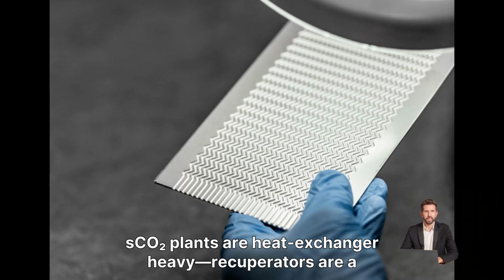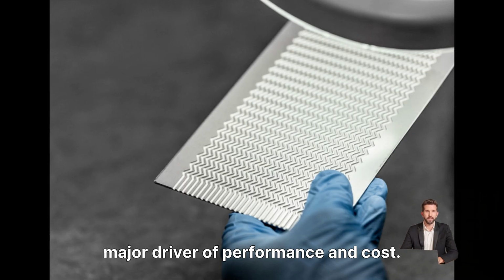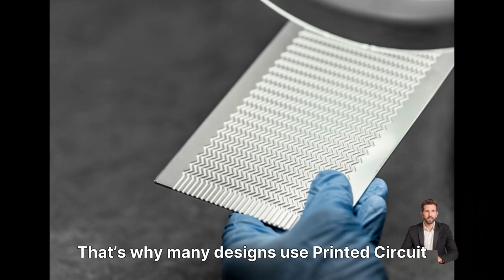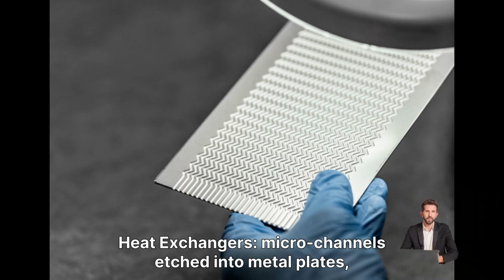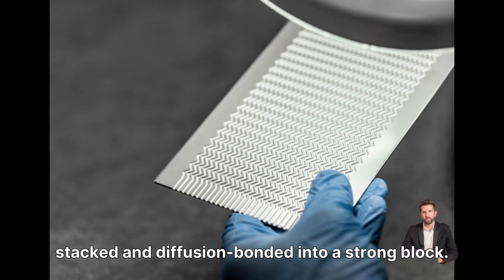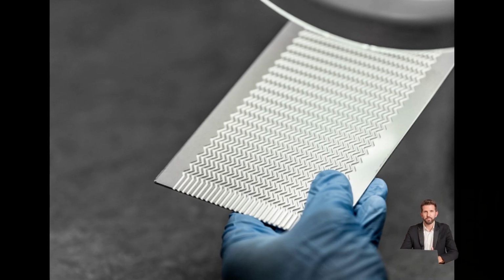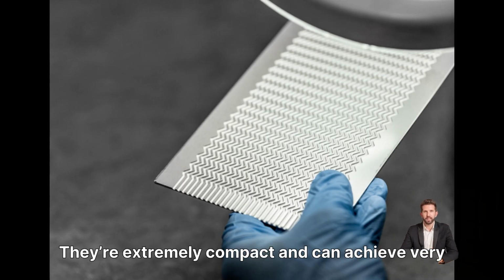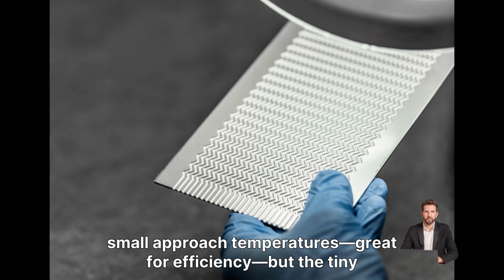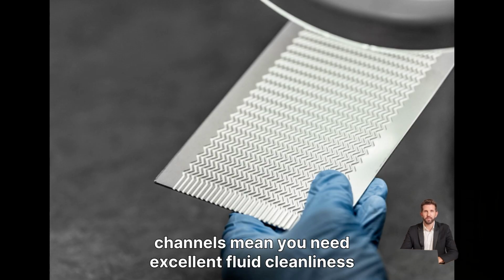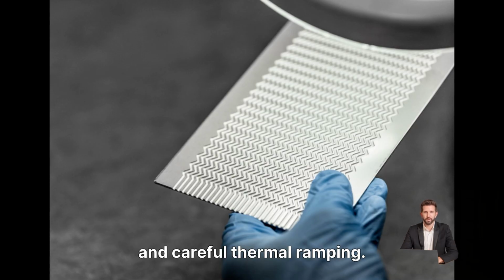SCO2 plants are heat exchanger heavy. Recuperators are a major driver of performance and cost. That's why many designs use printed circuit heat exchangers, microchannels etched into metal plates, stacked and diffusion bonded into a strong block. They're extremely compact and can achieve very small approach temperatures, great for efficiency. But the tiny channels mean you need excellent fluid cleanliness and careful thermal ramping.